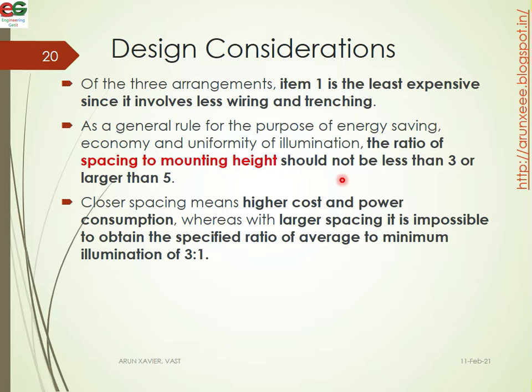Closer spacing means higher cost and power consumption. With very small spacing, we have higher power consumption and higher cost. With larger spacing, it is impossible to obtain the specified ratio of average to minimum illuminance.